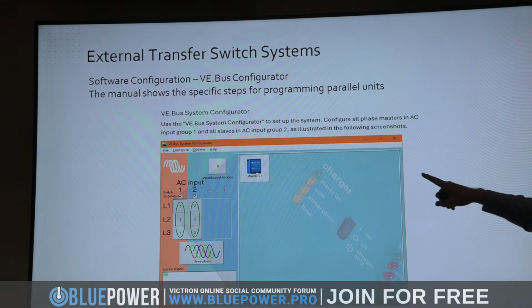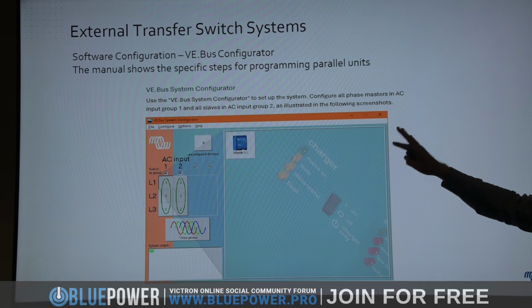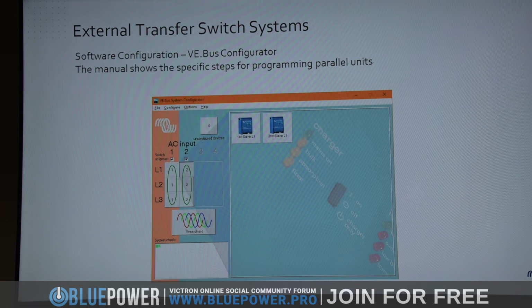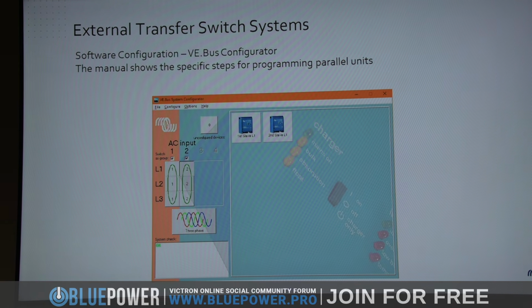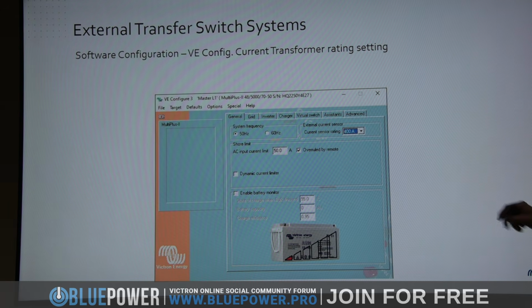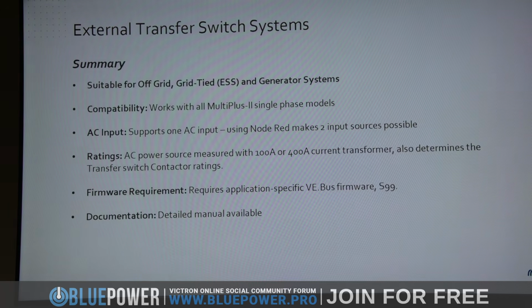In the manual, there's a very nice section that tells you how the VE.Bus configuration must work, step by step, how to configure it, the masters, the slaves. You must select your current sensor in the master. So in summary, it's suitable for off-grid, grid-tied, and systems with generators.